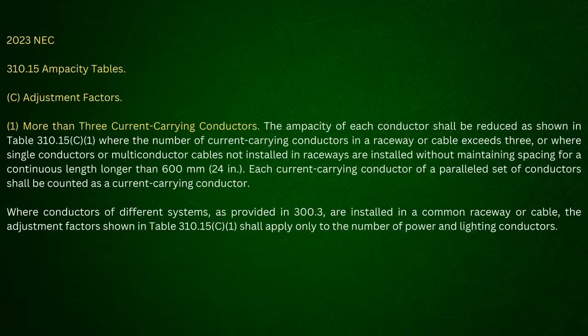But if I look at this and I look at (C)(1), it talks about more than 3 current carrying conductors. Now let's see what it says. The ampacity of each conductor shall be reduced as shown in Table 310.15(C)(1), where the number of current carrying conductors in a raceway or cable exceeds 3. So if I'm in a cable, the conductors in that one cable have to exceed 3. Now let's see what it says right after this. Or where single conductors, oh, looky here, or multi-conductor cables not installed in raceways.